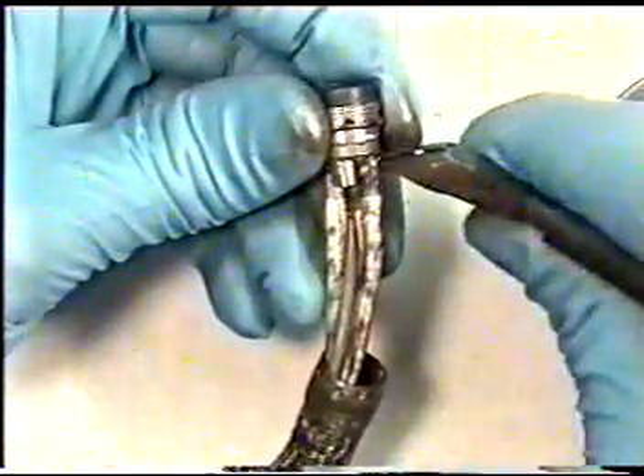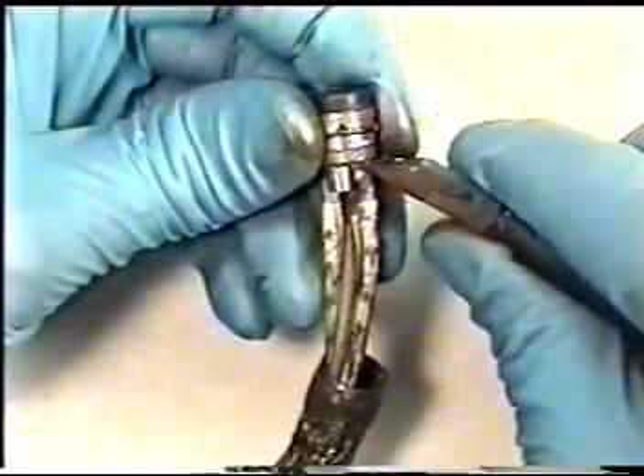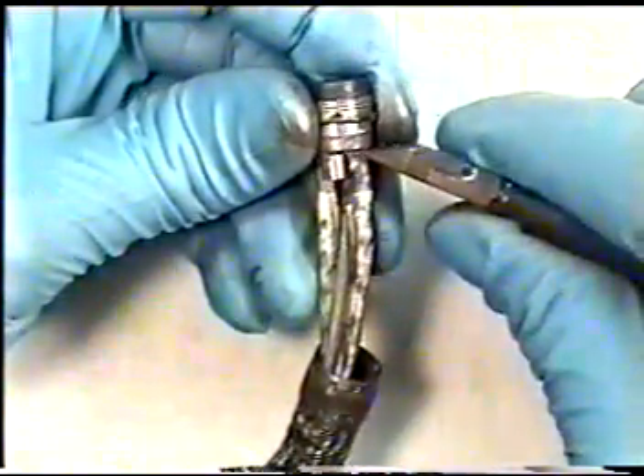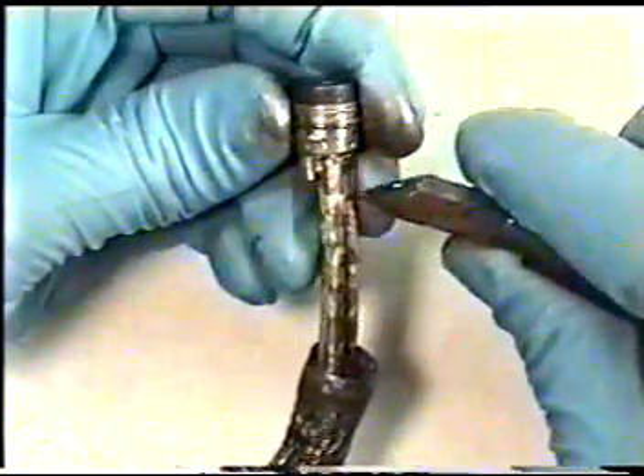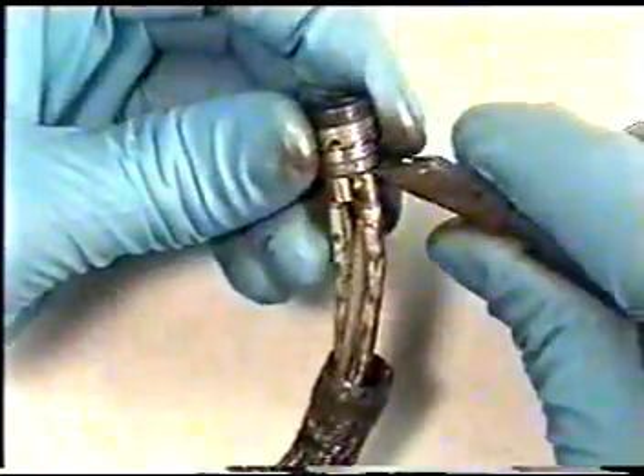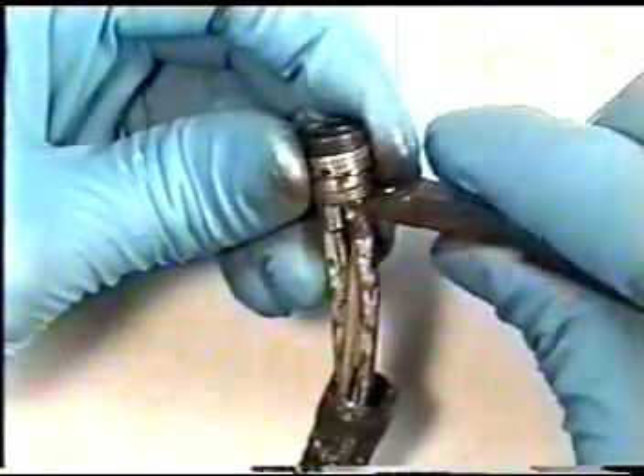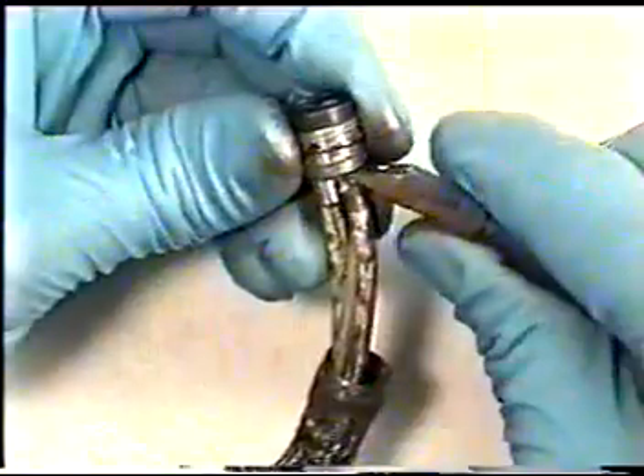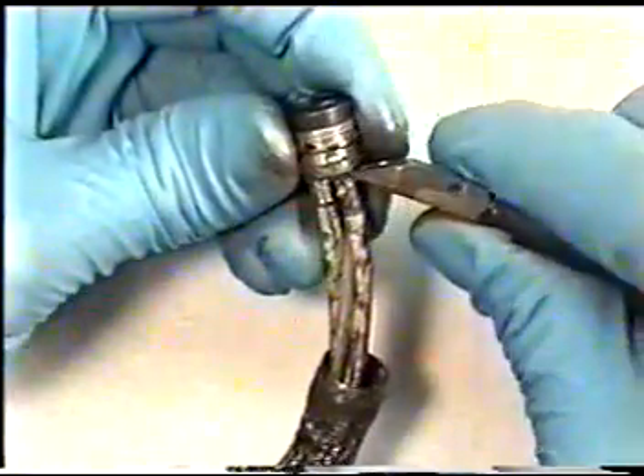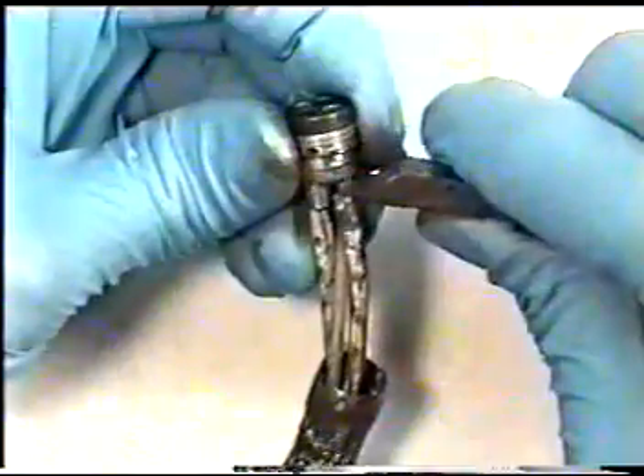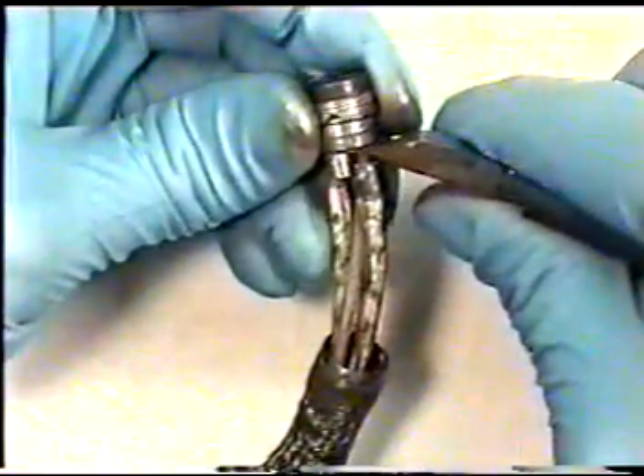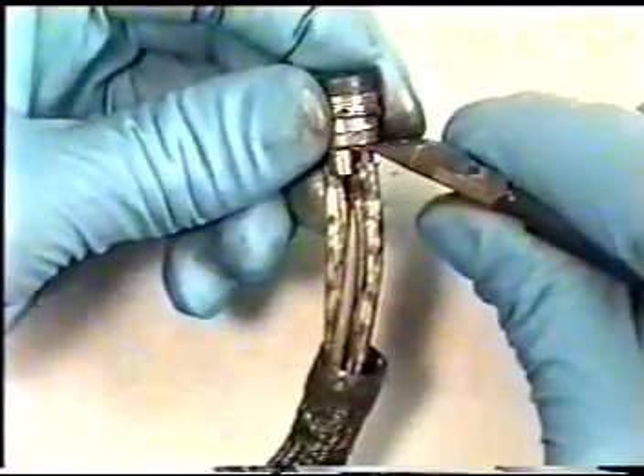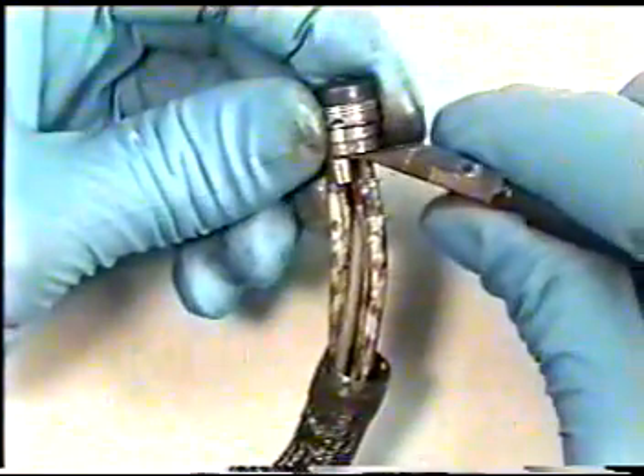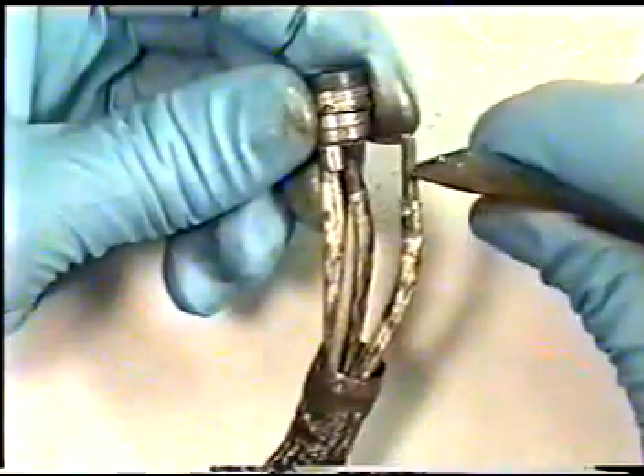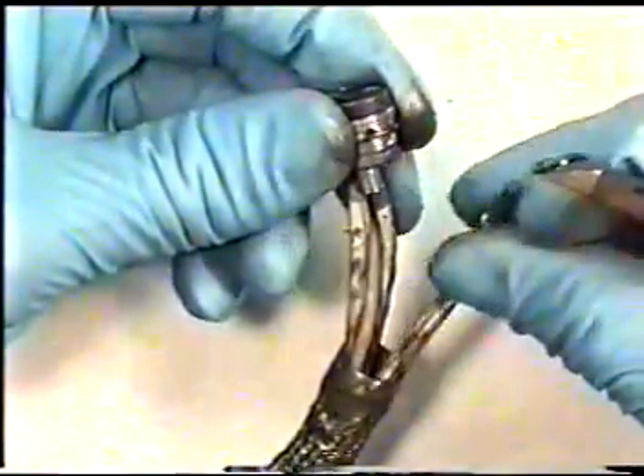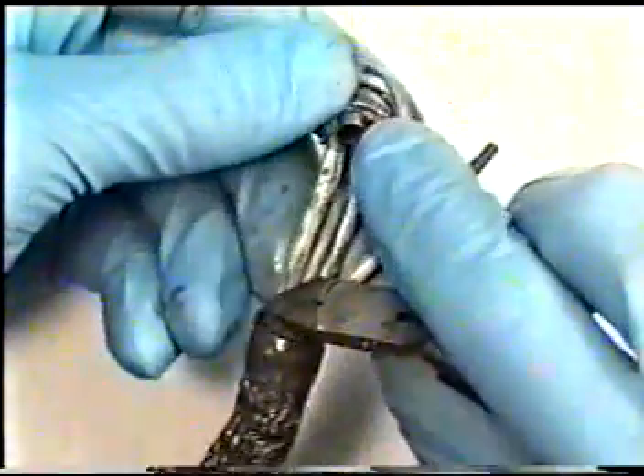This light guide is damaged, so you can apply some force to the post in order to pry it out, but not too much force where you will cut into any other important tube or wires. If the acetone's set and your pliers are carefully pulling, you should be able to remove the illumination light guide bundle from its distal end hole.